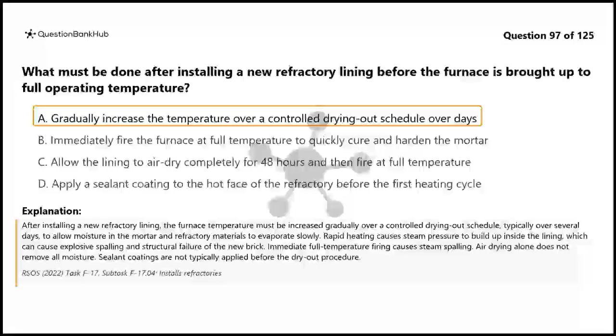Rapid heating causes steam pressure to build up inside the lining, which can cause explosive spalling and structural failure of the new brick. Immediate full temperature firing causes steam spalling. Air drying alone does not remove all moisture. Sealant coatings are not typically applied before the dry-out procedure.